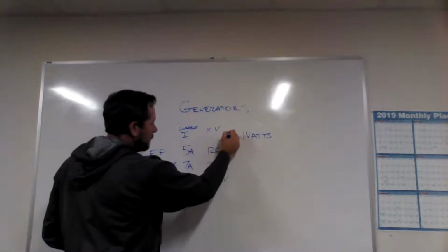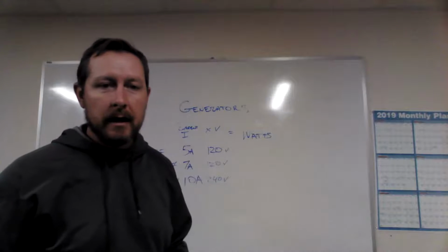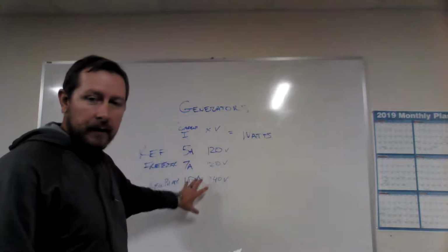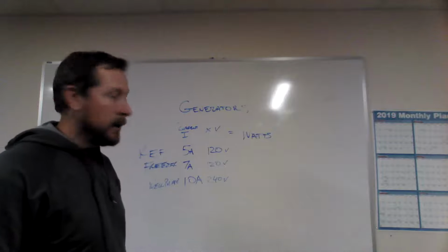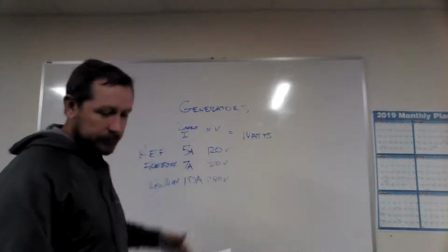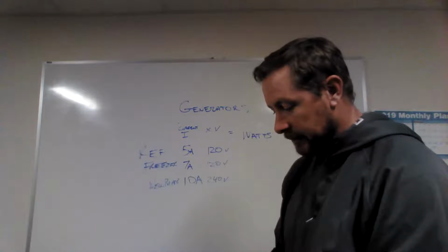Your current, or I, so current, times your voltage equals your watts. That's an important formula to understand and to know. Knowing that, once you start figuring out what you want to run from your generator, you can size your generator because you have the information you need to get there. So I'm going to grab a calculator real quick so I don't have to just do this in my head.